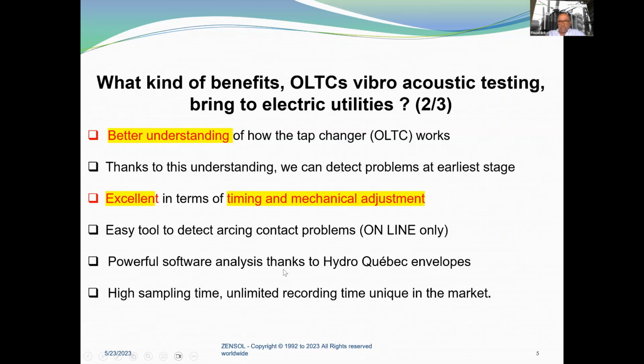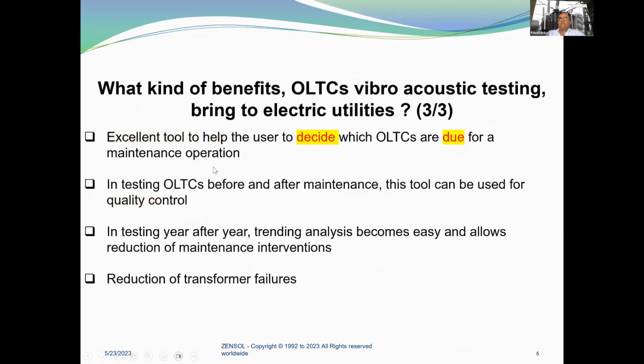We have a software, and thanks to Hydro-Quebec envelopes, we are able to detect a lot of problems. We have a high sampling rate and an unlimited recording time, which is unique in the market. It's a quick tool that helps the user decide which OLTCs are due for a maintenance operation. And by testing OLTCs before and after maintenance, this tool can also be used for quality control.